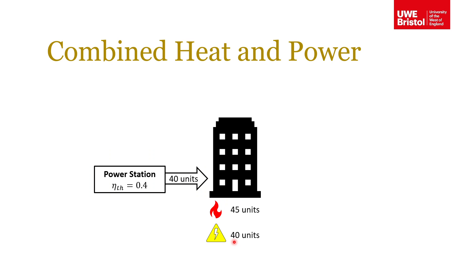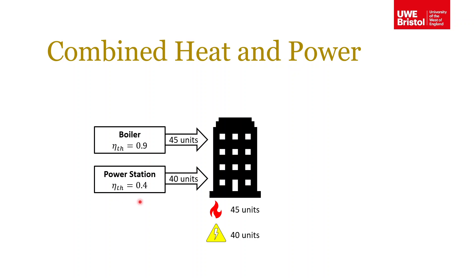Conventionally, the power supply to this building would come from the power station, giving us our 40 units of electricity. The thermal efficiency of a power station, as we know from thermodynamic cycle examples such as the Rankine cycle, is around 40 percent. We've also got a boiler supplying heat to the building, giving us our 45 units of thermal energy. Boilers tend to have higher thermal efficiency.